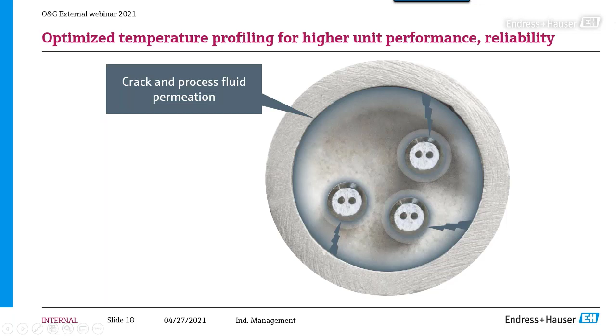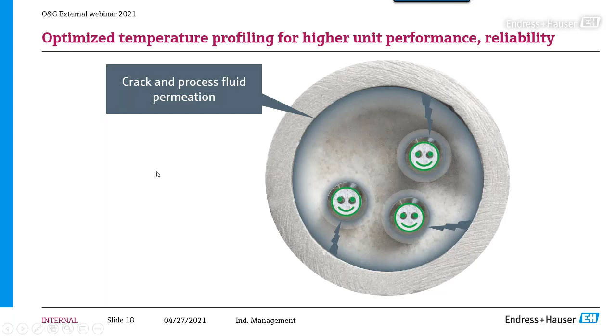And then if we have again the pollution of the powder, this pollution will spread all inside the area of the thermocouple and reach the inner wires. But because of the inner protections, which are 1, 2, and 3, nothing will happen to the inner sensors. This is the very innovative thinking: we have increased the number of metal barriers from 1 to 2, so that any pollution of the powder cannot contaminate and affect the temperature measurement. This goes in the direction of sensor reliability and also safety of the plant.